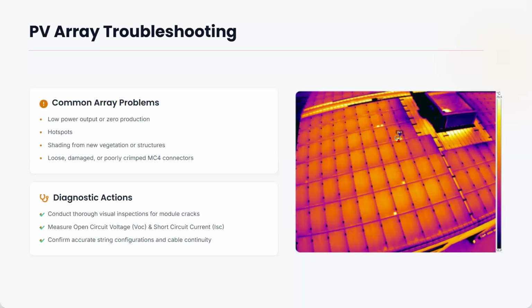Then let's look at the diagnostic action. Conduct thorough visual inspection of module cracks. This is physical. If you get to the roof, you can see where the panels are, where cracks are on the panel. And then if you have that, it can lead to the hotspots that we mentioned, and then it will lead to poor performance of the solar panel. So you can see cracked cables, that could lead to leakage at the end of the day. So then you correct them, and then the system continues to perform well. But the most important thing is to get good quality of all these things, so that you also get quality peace of mind.